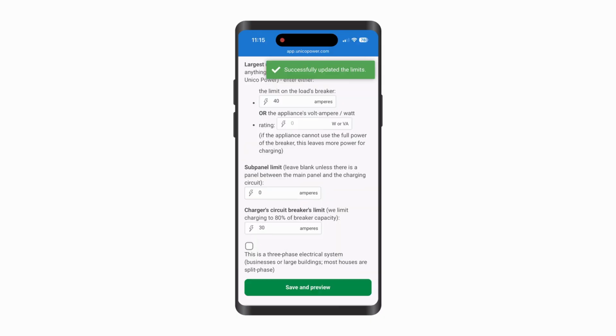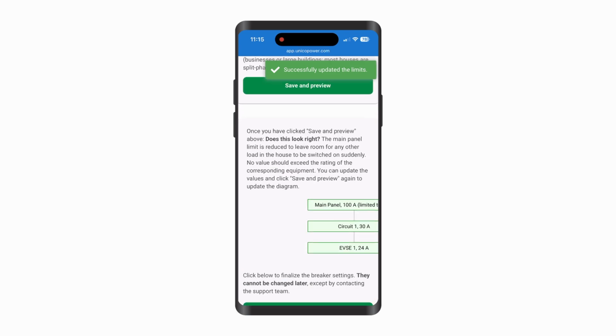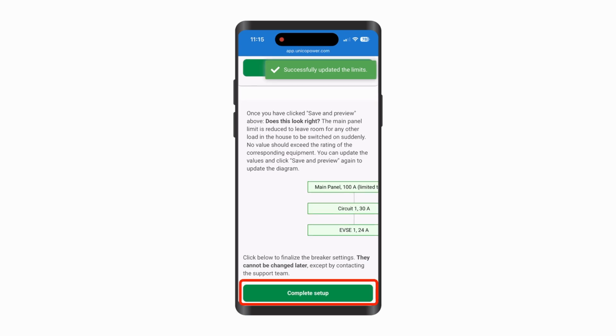You must set the fail-safe limit for the EVSE. It is set to 0 by default, so if there is 6 or more amps of capacity on the panel, be sure to set it to 6. Click Save and Preview. Confirm the limits are correct, and select Complete Setup.